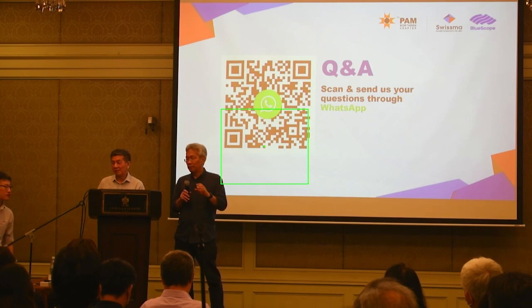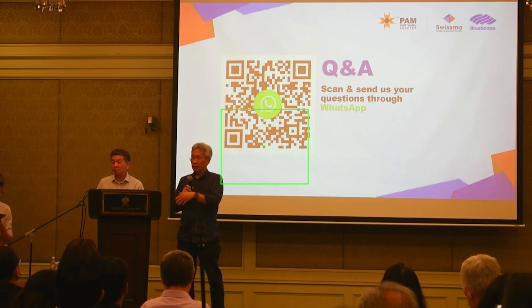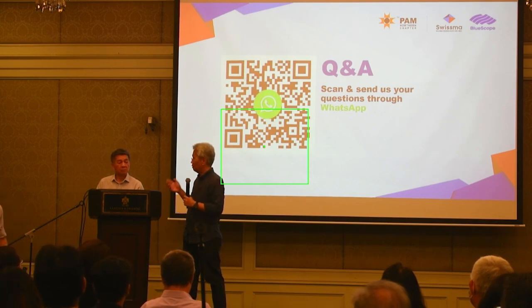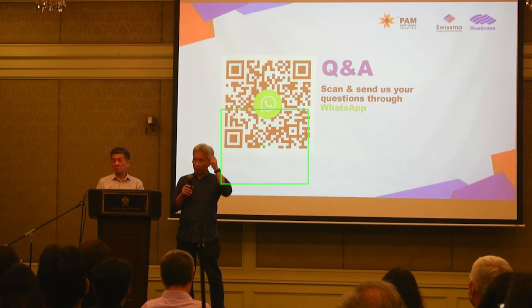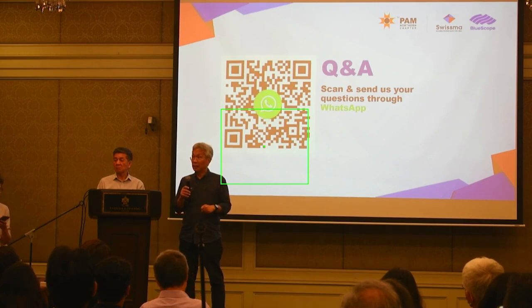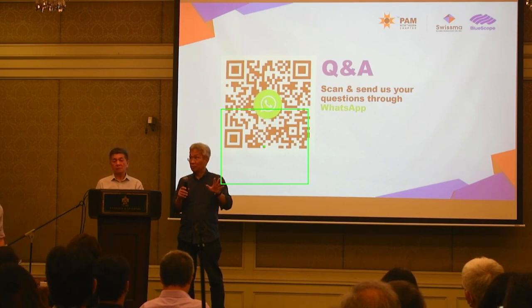The intention has always been there, and of course, in the eyes of the law, when it's gazetted, it has to have a date with effect, and be retrospective. But our Uniform Building Bylaws are an entire document, so Bomba could not isolate that part. The August 2021 directive mentioned that it is with immediate effect for all new building submissions, and for buildings not completed as of that date, they are subject to it. That's why during that time a lot of projects got frantic, because everything was coming onto the site and they had to retrospectively get the test. As for existing buildings, they did say they want all buildings with cladding systems to be reviewed.